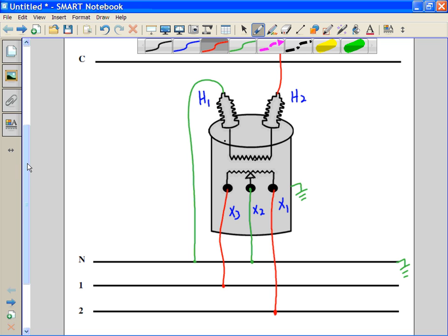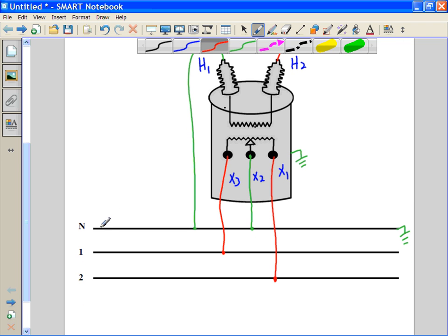So now we have to determine what our voltages will be when this transformer is energized, from neutral to line 1. If you're not sure what these voltages are, the best thing to do is follow them back to the transformer. So the neutral, follow it back, we end up at the X2. And line 1, if we follow it back to the transformer, we end up at X3. And we see that measurement then, the voltage is half of this coil. Half of this coil should equal 120 volts. Neutral to line 2, we have the same situation. In this case, we're measuring voltage from the X2 to the X1 position. Again, half of the coil should equal 120 volts.